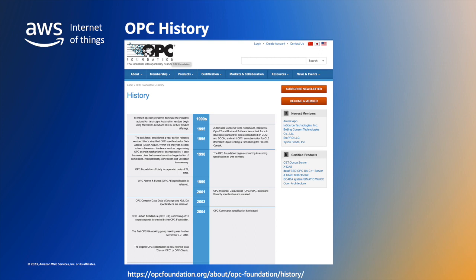The early specifications included OPC DA Data Access, the initial specification, OPC AE Alarms and Events in 1999, OPC HDA Historical Data Access in 2001, and finally OPC UA Unified Architecture around 2008, which incorporates all the previous Classic specifications for DA, AE, HDA, etc.